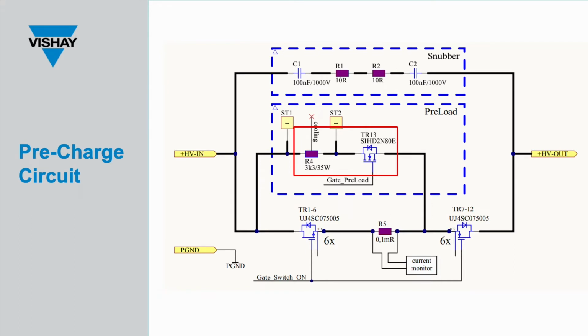In the first stage, the MOSFET is energized, and after 25 milliseconds, the output voltage is measured to see if it is greater than 10% of the input voltage. If the output voltage remains close to 0 volts, a short circuit condition exists in the load, the pre-charge stage is terminated, and an error is displayed. If the first stage is successful, the pre-charge will continue.